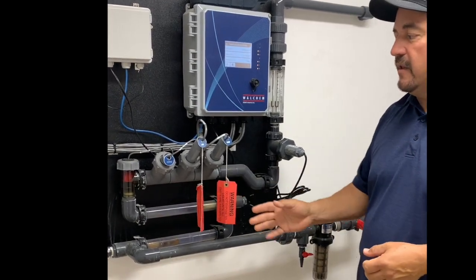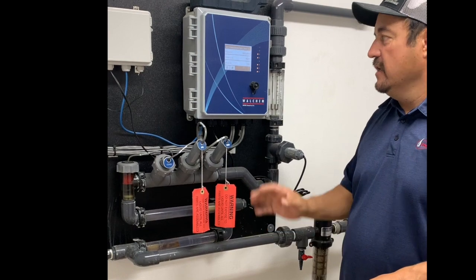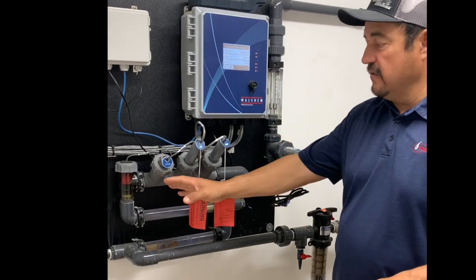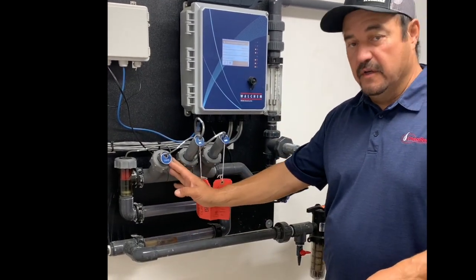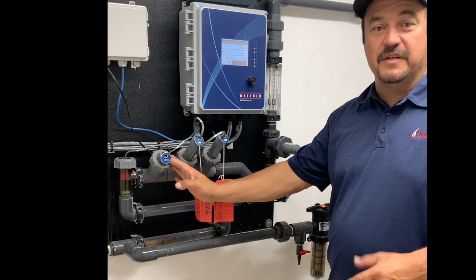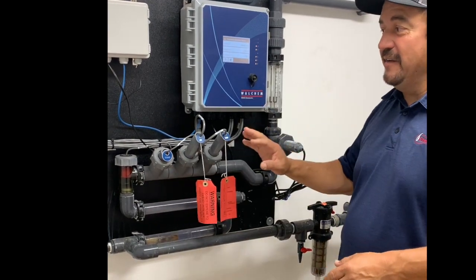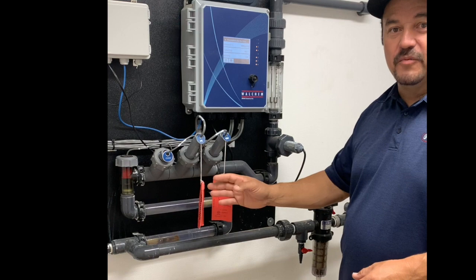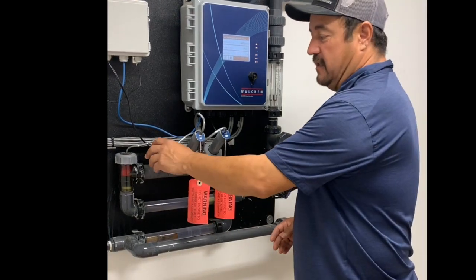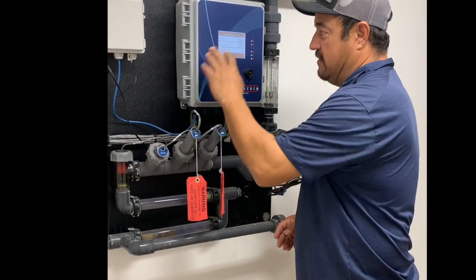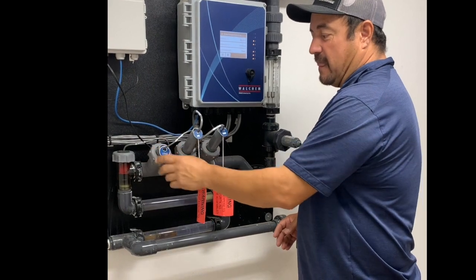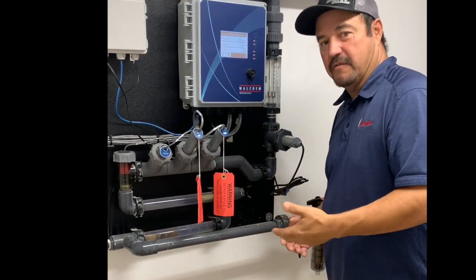Now, whenever we're doing a calibration, any type of calibration, before you calibrate the unit or the actual probe, you want to make sure that the probe has been cleaned. So you don't want to calibrate anything unless you know that the probe's clean. If I were to go in and calibrate this unit and the probe's dirty, it would throw my reading off, right?